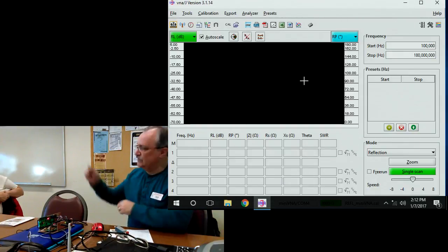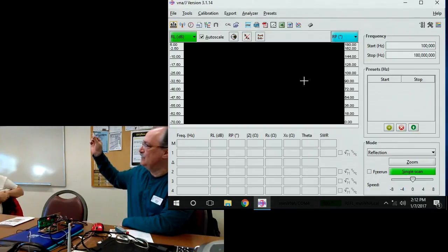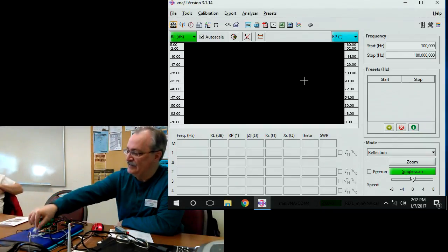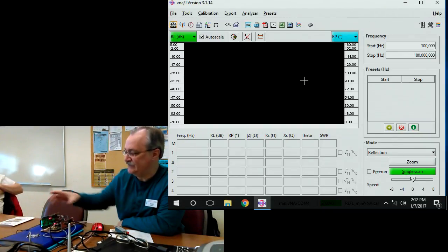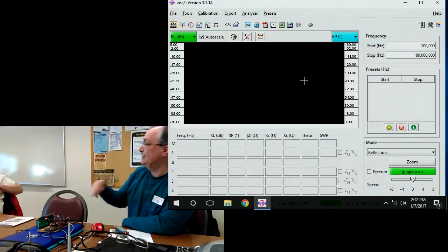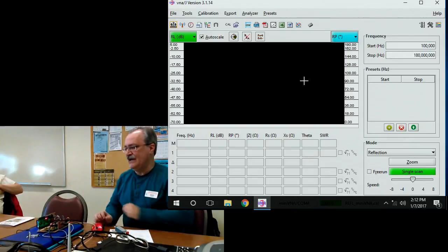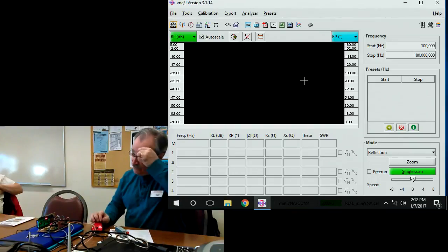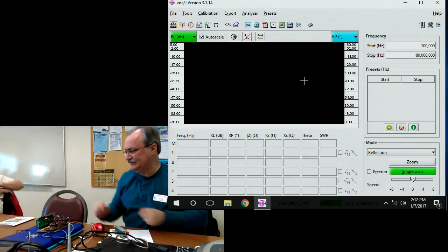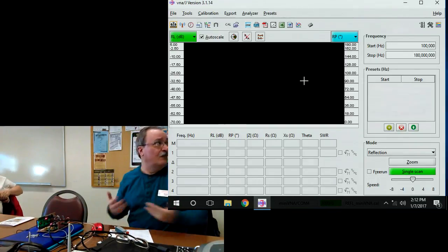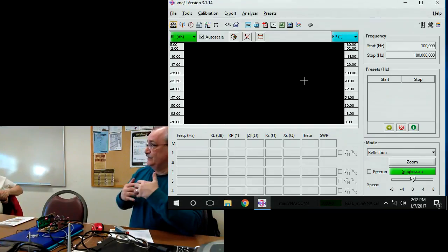I use just a little jumper here. This is just something I pulled out of a parts unit that's just some RG141 semi-rigid with a couple SMA connectors on it, and put that across both the device under test port and the detector port on the VNA. And then you also calibrate it with an open, which is just as it sits. Once you've got that calibrated and you've done the frequency count calibration, then you're set to go.